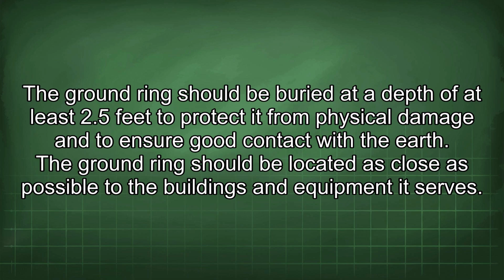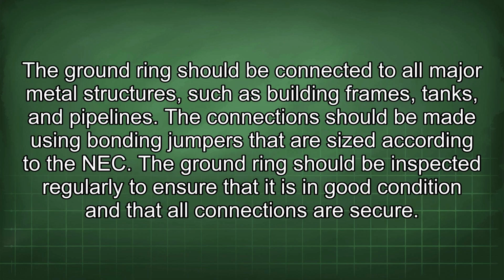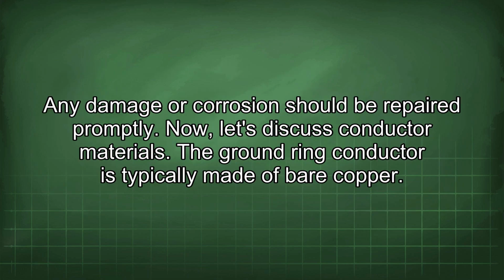The ground ring should be located as close as possible to the buildings and equipment it serves. The ground ring should be connected to all major metal structures, such as building frames, tanks, and pipelines. The connection should be made using bonding jumpers that are sized according to the NEC. The ground ring should be inspected regularly to ensure that it is in good condition and that all connections are secure. Any damage or corrosion should be repaired promptly.